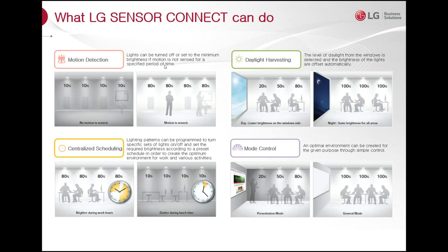Next we have centralized scheduling. With the use of our switch, you can schedule the light levels to be on or off, and customize what those on levels are. For example, if the offices should be on at 80% at 7 a.m., you can schedule that at 7 a.m. the lights turn on to 80%. If you want to drop them down, you can schedule the evening to turn on at half that brightness, and then schedule them to turn completely off at the end of the night.